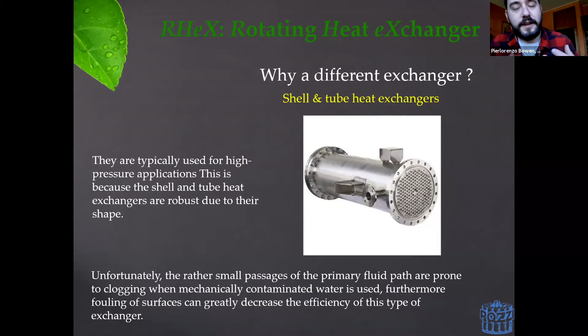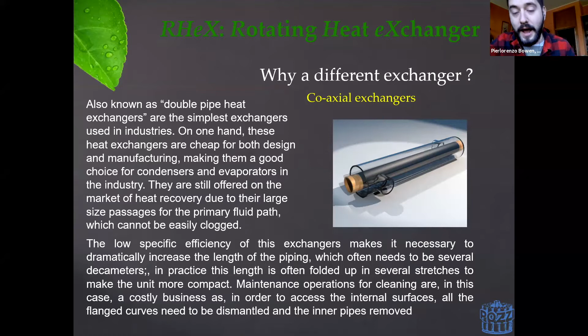A different type of solution is, for example, in coaxial heat exchangers, where they have a wider passage of area to allow for the bigger mechanical pollutants to pass through easily. The drawback of this is that obviously you're going to lose a lot of efficiency because, as I said before, velocity is directly proportional. Actually, it's the other way around. Efficiency is directly proportional to the velocity of the fluid. And so with a wider cross-sectional area, you're going to lose efficiency. And as well, you're going to run into the problem of fouling.